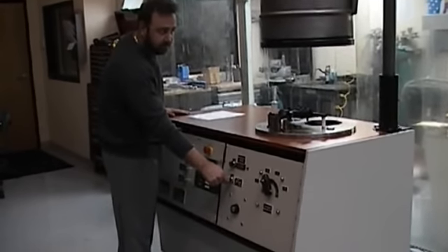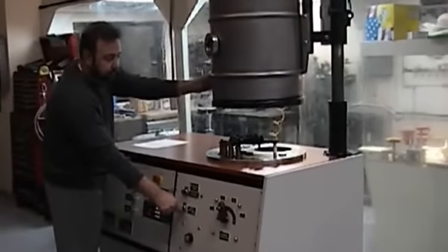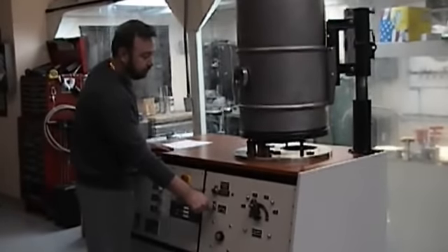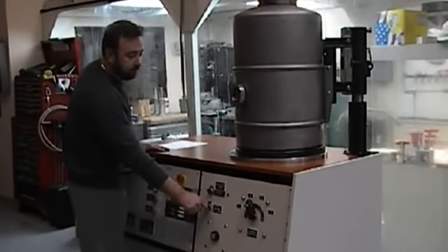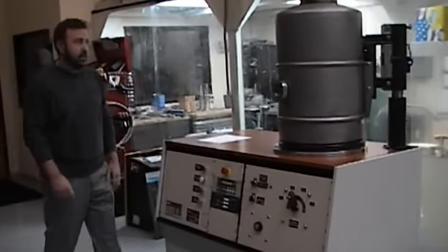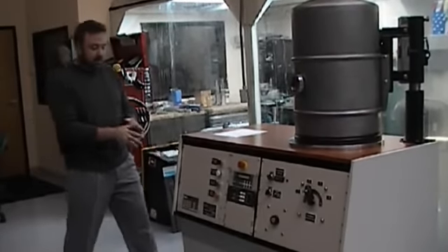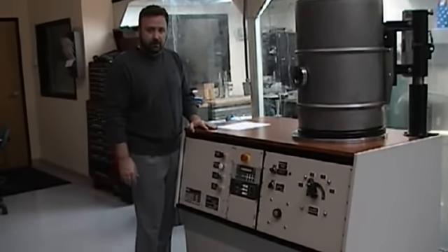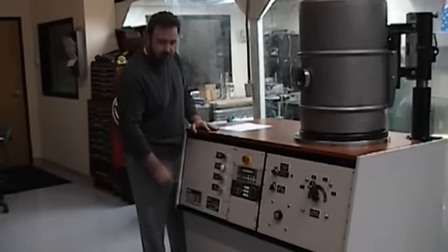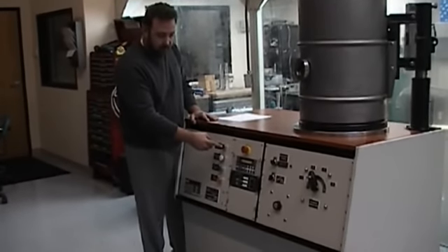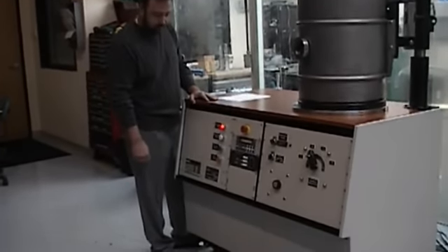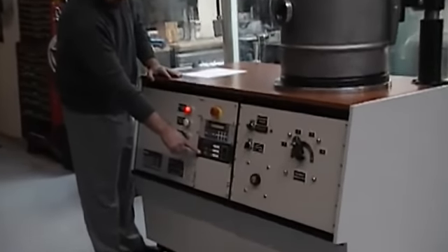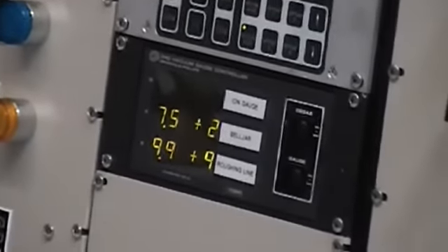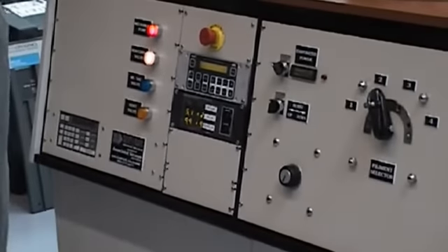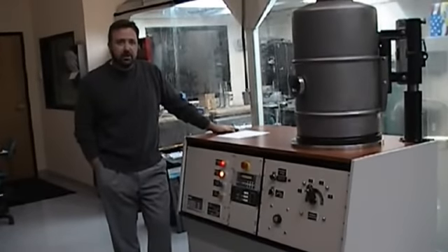Okay, down position. Again, automatically stops. Gets down to lock position. At this point, I'm going to repeat the process that we did before. Our red, white, and blue switches in order. So we turn on our mechanical pump. And we'll go ahead and turn on our white, which is our rough valve. We previously did the demonstration.